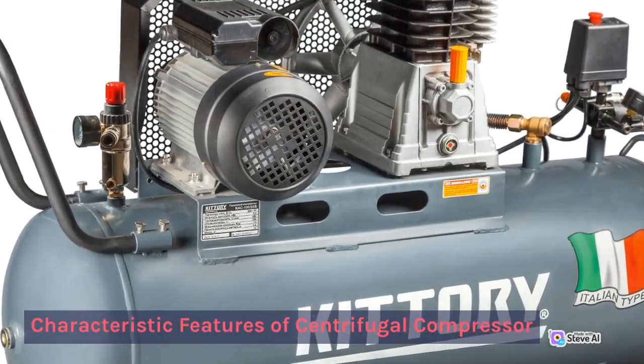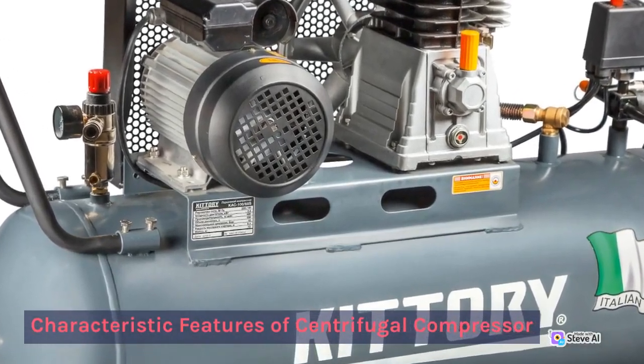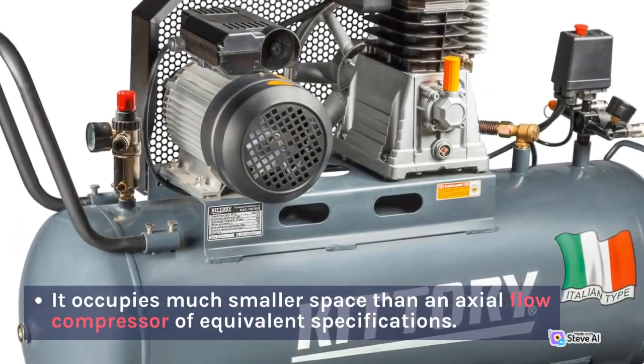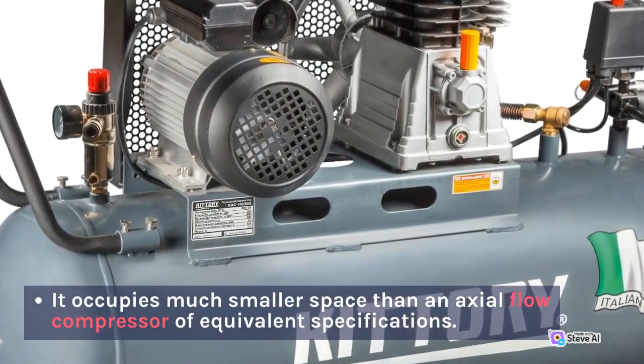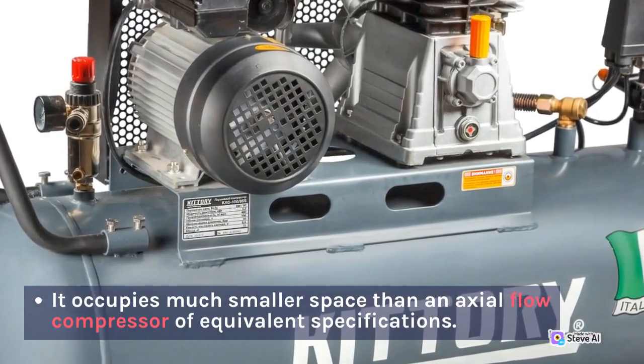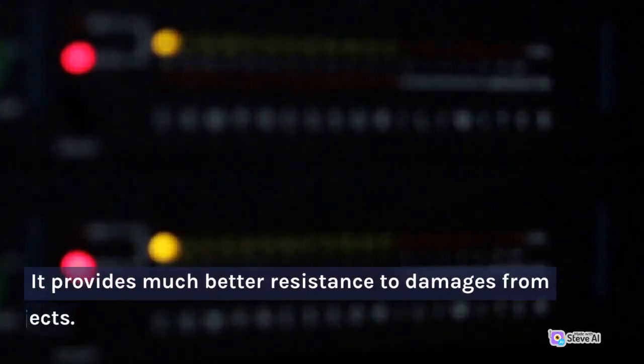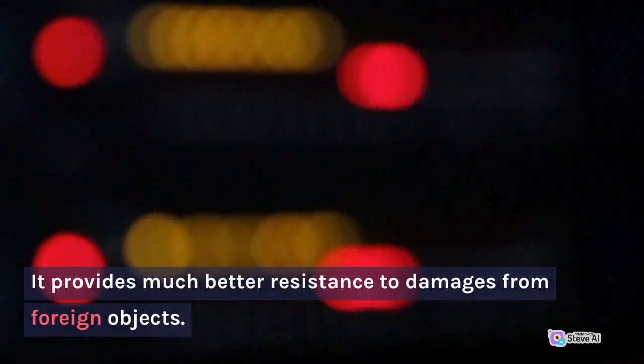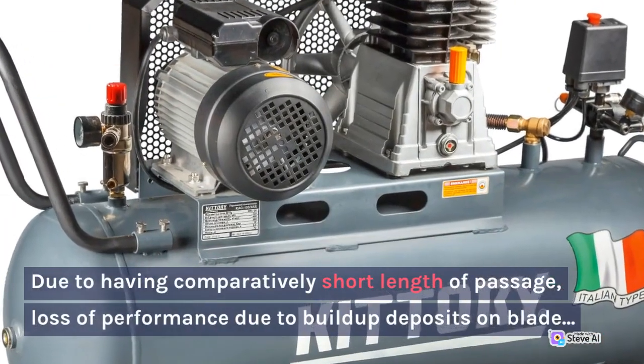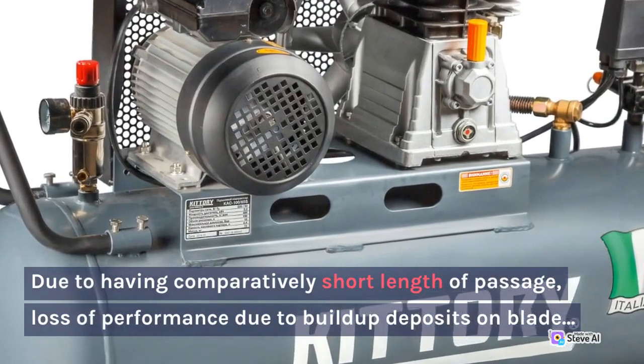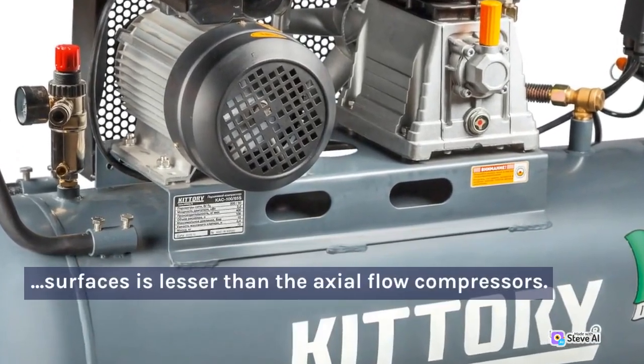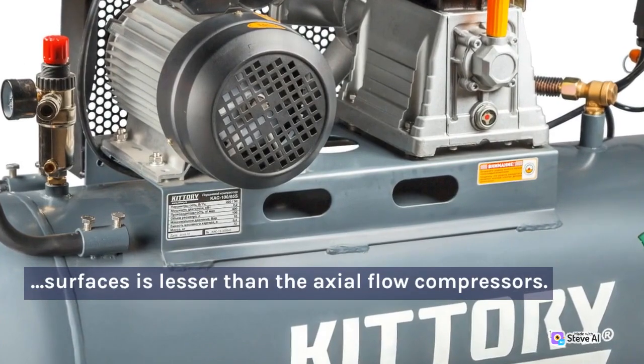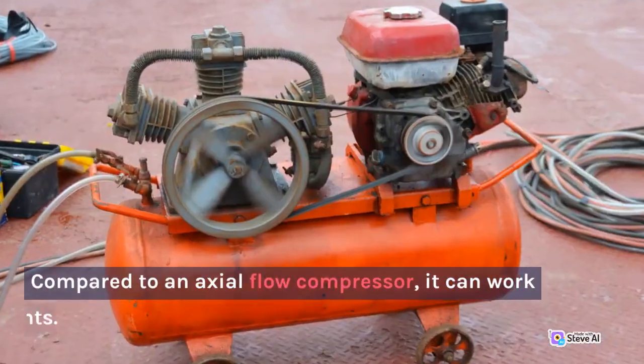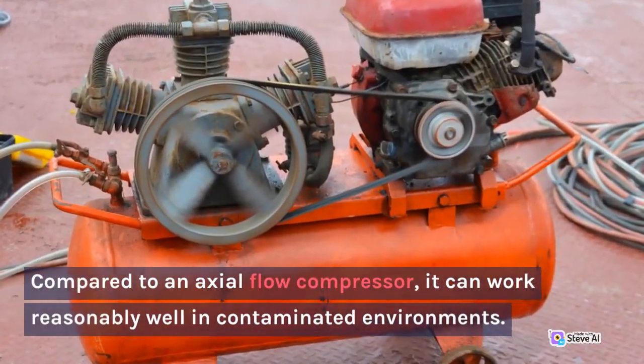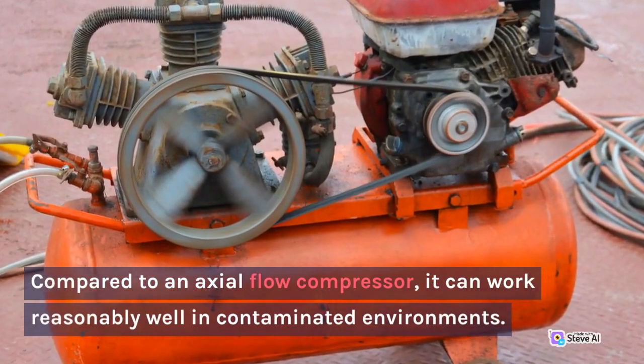Characteristic features of centrifugal compressor. It occupies much smaller space than an axial flow compressor of equivalent specifications. It provides much better resistance to damages from foreign objects. Due to having a comparatively short length of passage, loss of performance due to built-up deposits on blade surfaces is lesser than the axial flow compressors. Compared to an axial flow compressor, it can work reasonably well in contaminated environments.